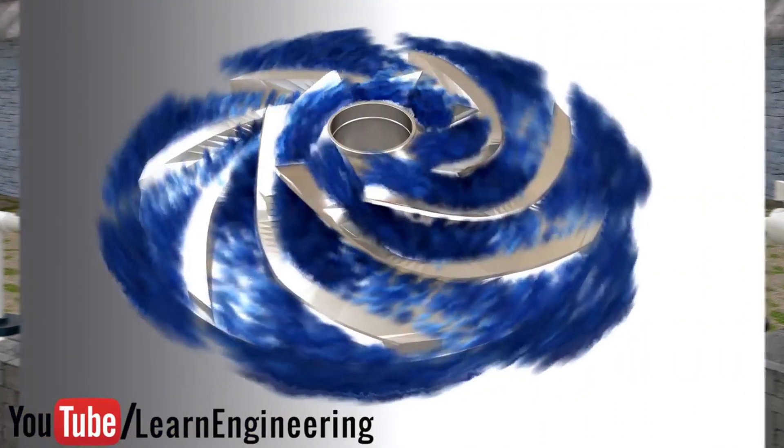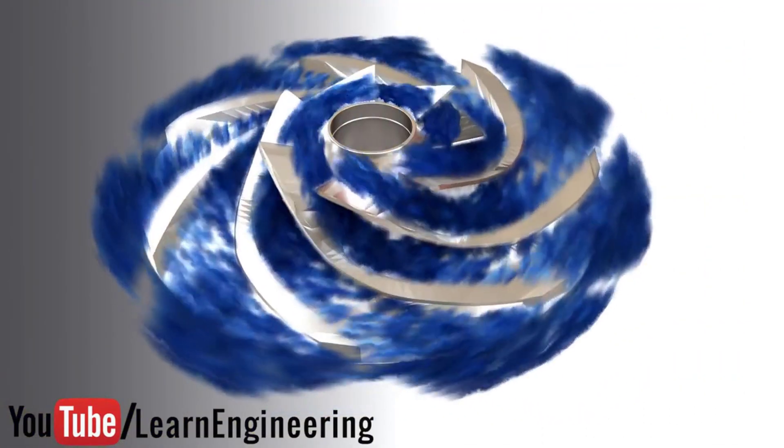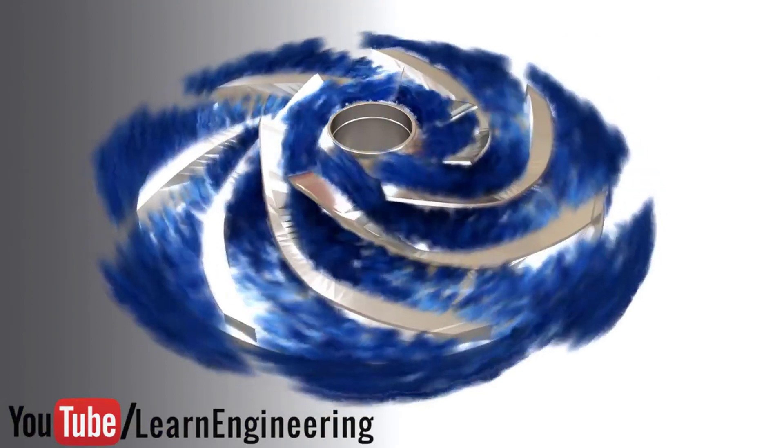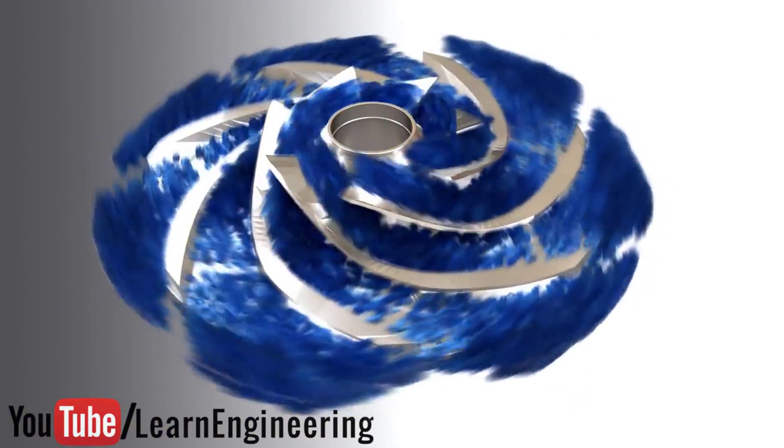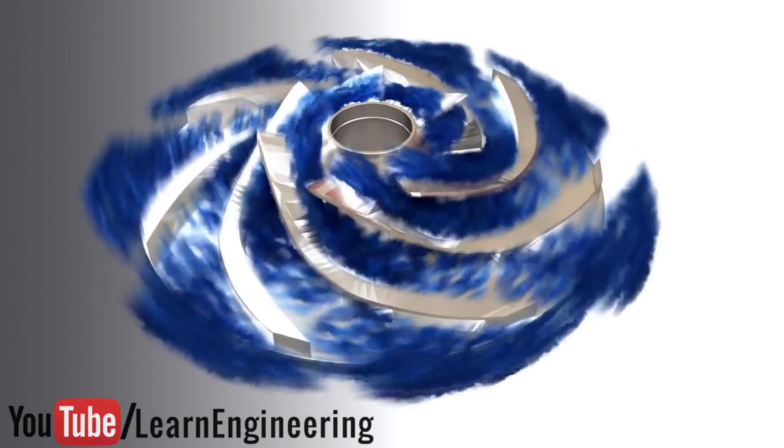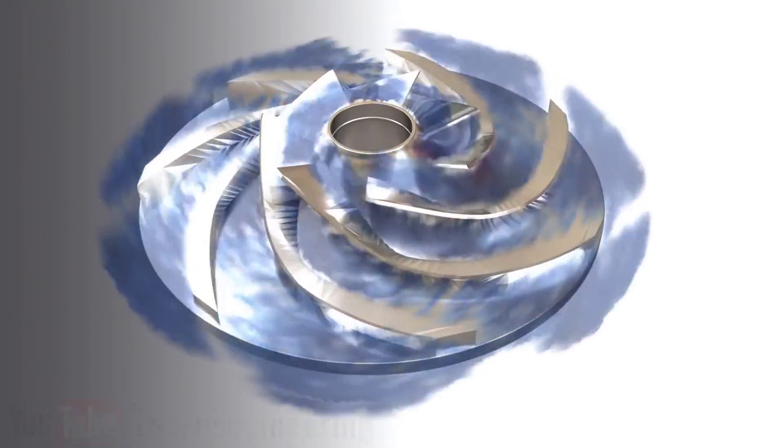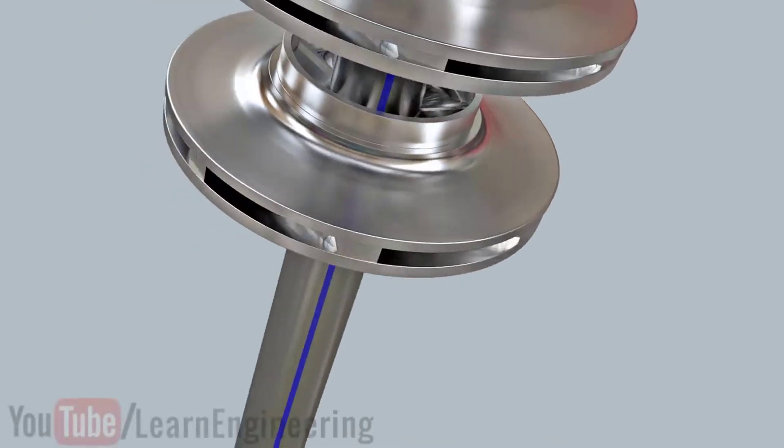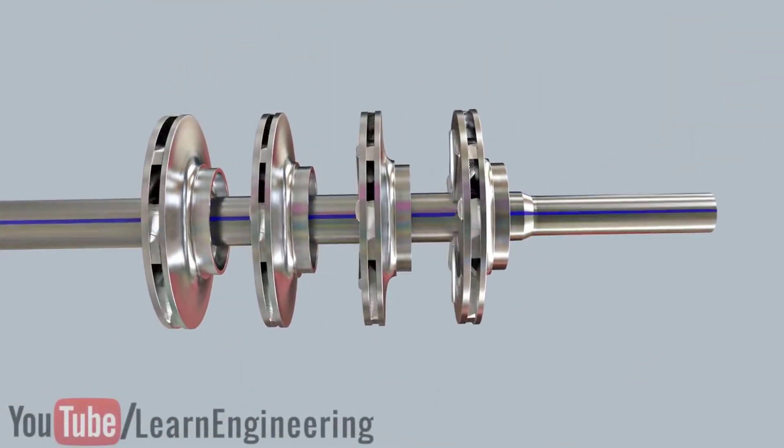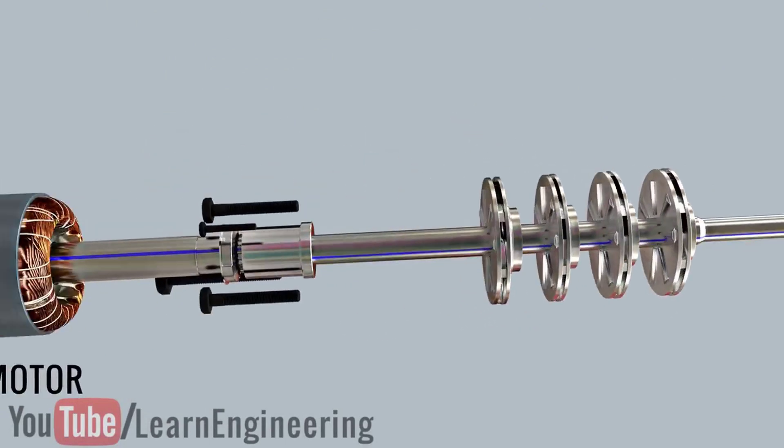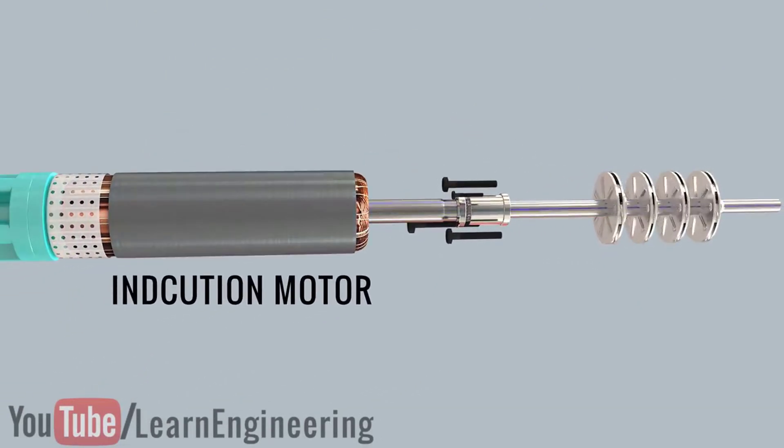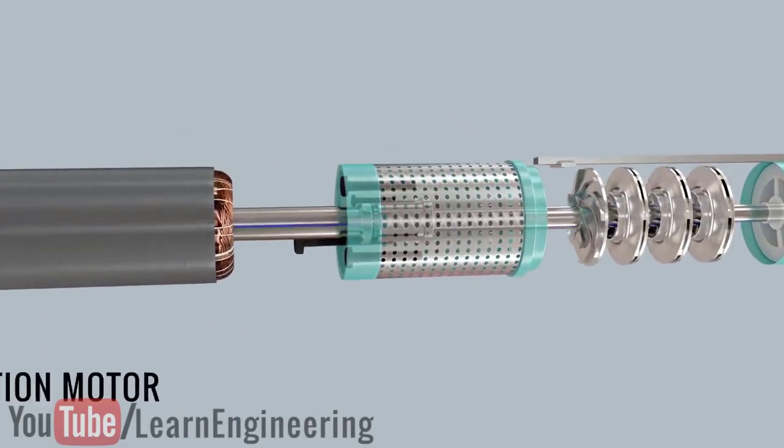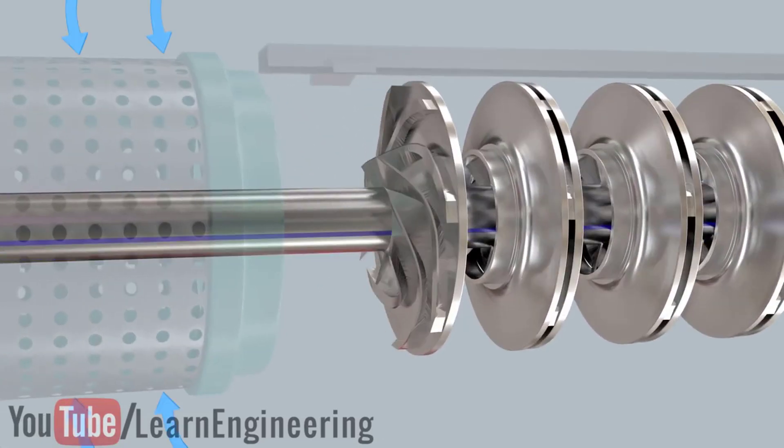The submersible pump is a centrifugal pump. You can see how the impellers are throwing the water outwards. The impeller blades are the backwards curve type. Here, many of the impellers are connected onto a single shaft, and this shaft is driven by an induction motor.